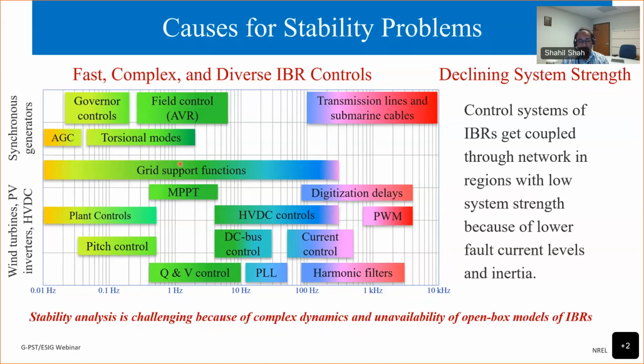So we have very fast and dynamic-rich devices that we are continuously adding to our power systems. They are complex. It's hard to describe this behavior by a few differential equations, which we can do with synchronous generators. So they are highly complex and they are diverse. Each manufacturer will have their own set of control codes, and if not thousands, a few hundred lines of code decide how these inverter-based resources behave during different grid events. So the complex controls are one part of the problem, and the second part is declining system strength. With reduced system strength, the dynamics of all these IBRs get coupled, and that is the reason why we see these oscillation issues.